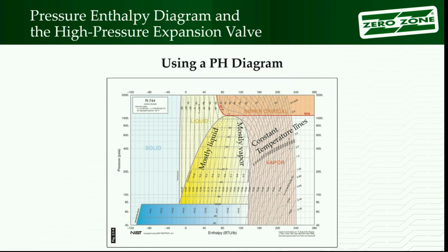And as a refrigeration engineer, very, very useful. But what we're really going to be concerned with as it relates to the high pressure valve, we're going to be concerned, like I said, mostly liquid on the left-hand side, mostly vapor on the right-hand side. When we follow our temperature lines, where is that going to drop in? Am I going to drop in on the liquid? Am I going to drop in more over by the vapor side?